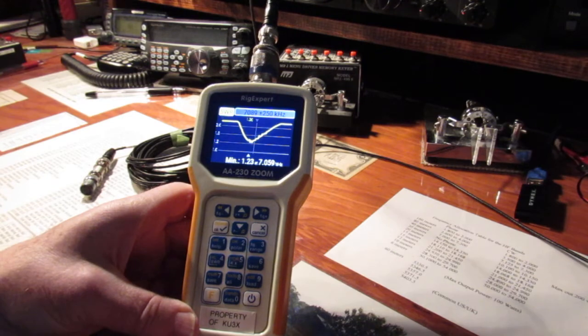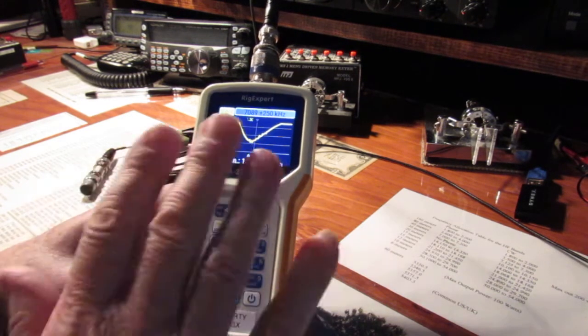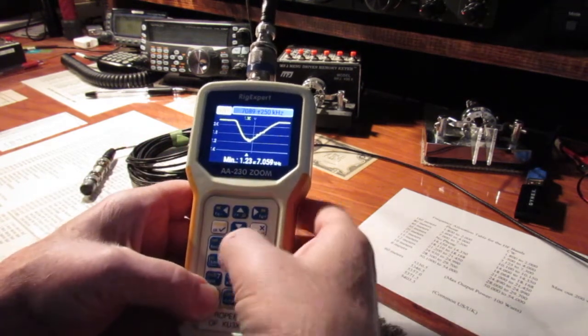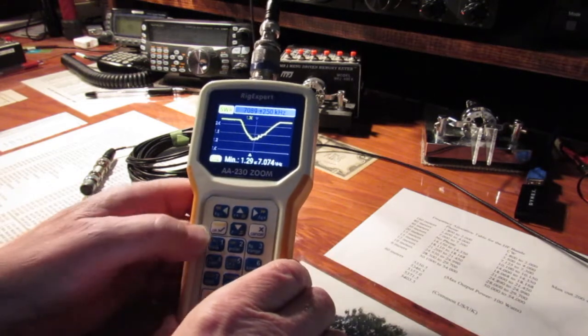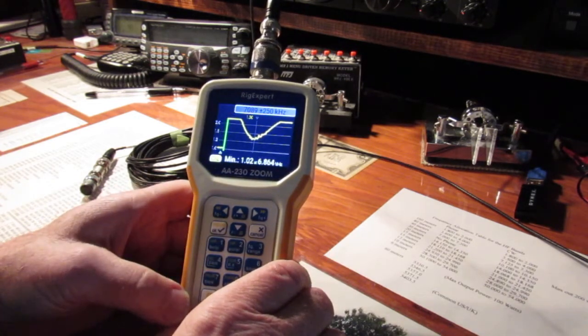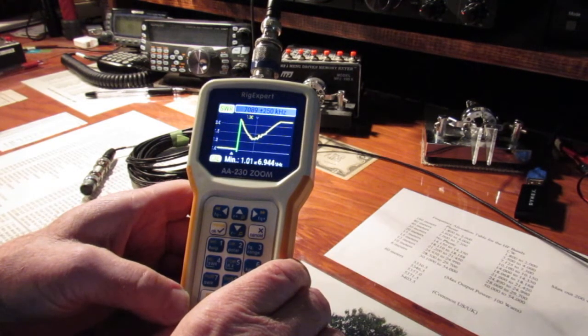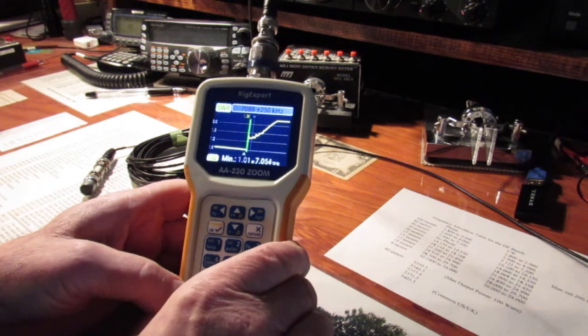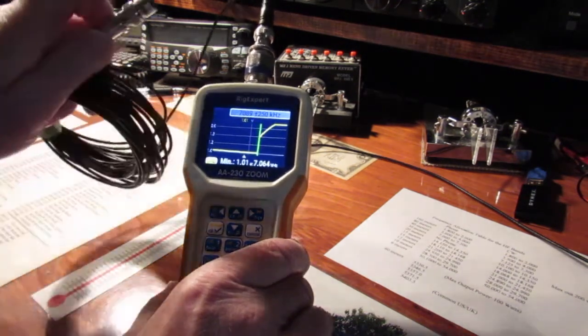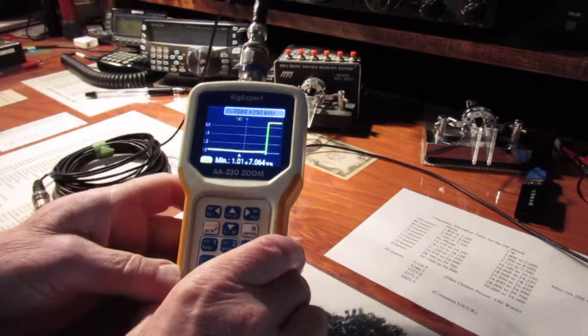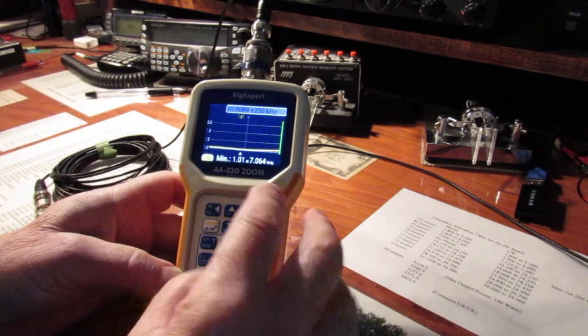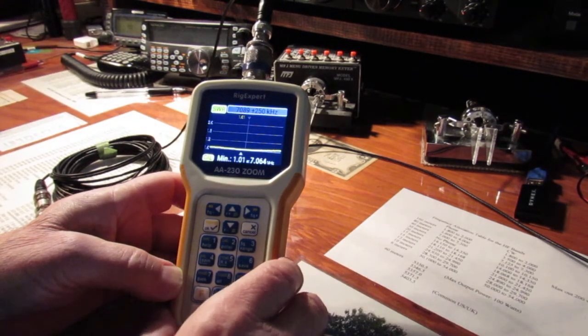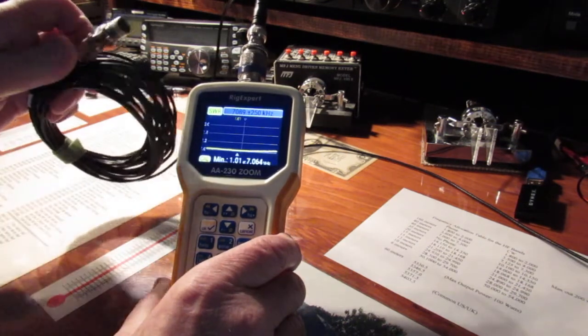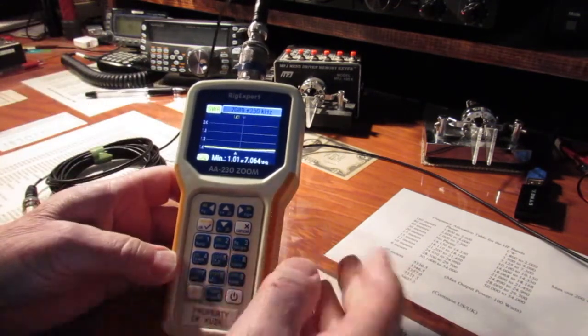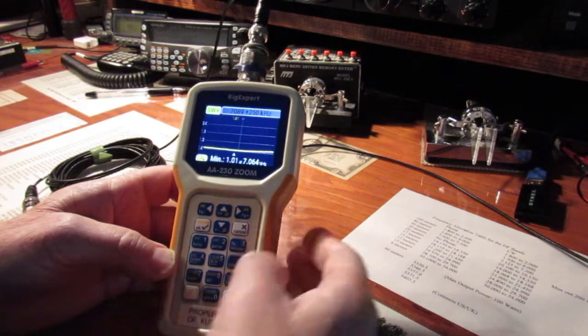So if you did the 10,000 sampling points, you can save it. So now you want to turn it back on. Let's do a sweep. Now, remember, that's what we're reading. That 50 ohm load, it's not hooked up to anything, so it stays down at the bottom. That's as close as you're going to get. Remember, this is 49.9 ohms, not 50, so you do get a reading. So that's open short load calibration.